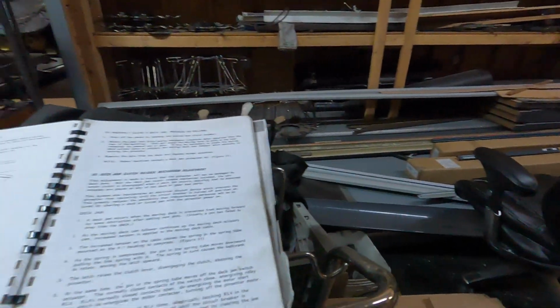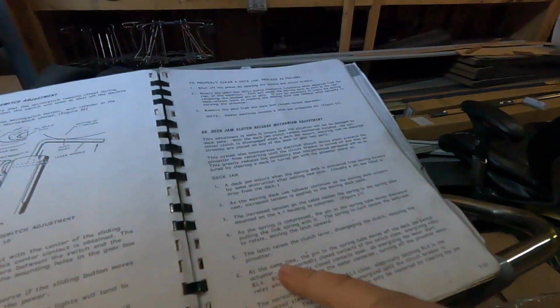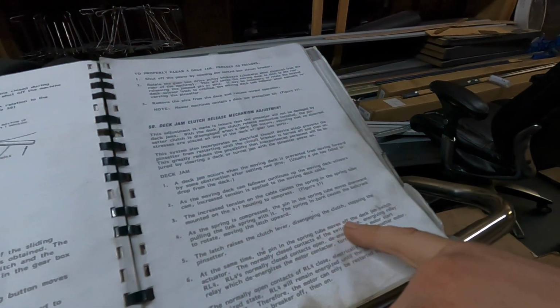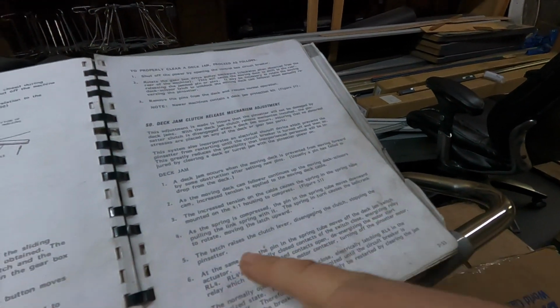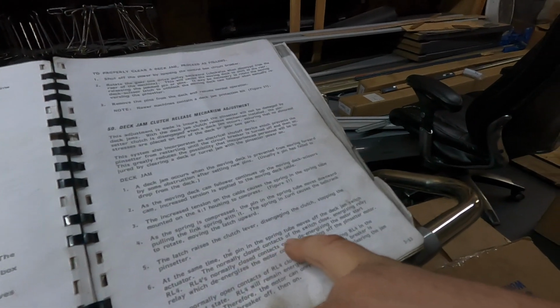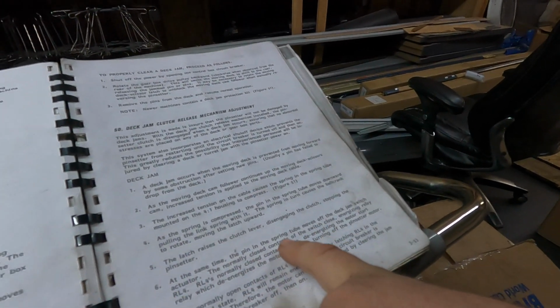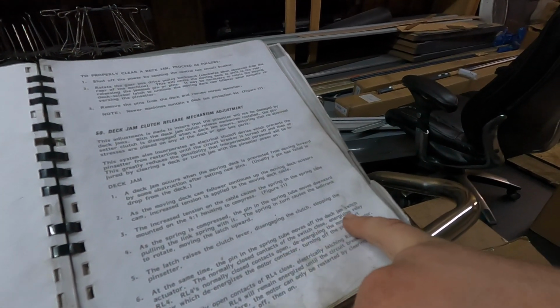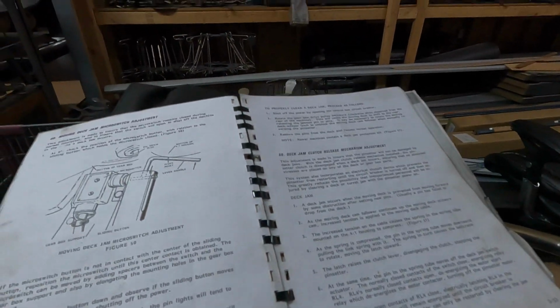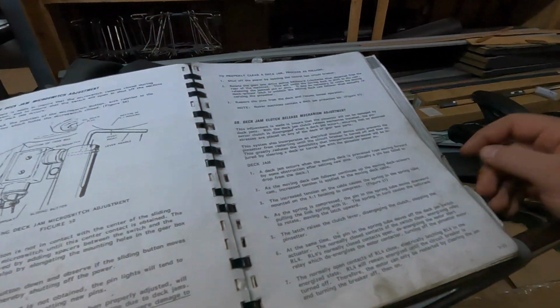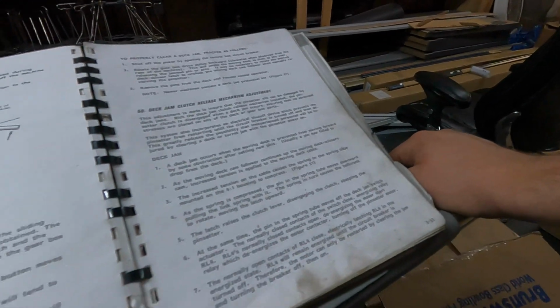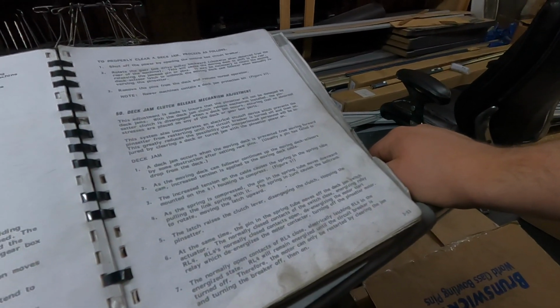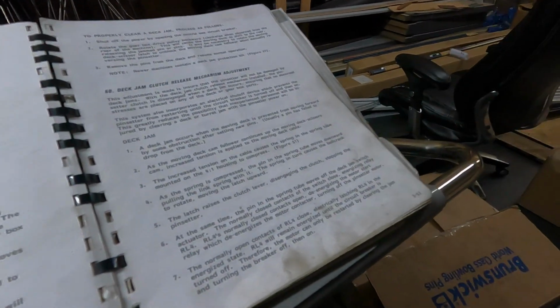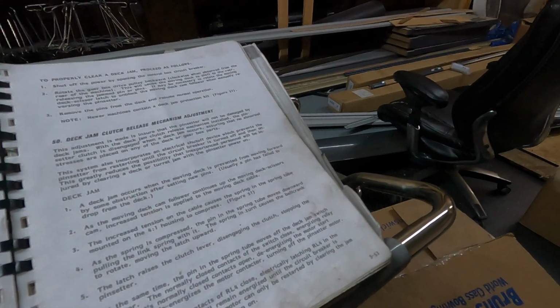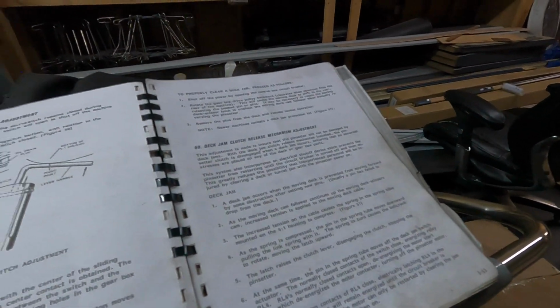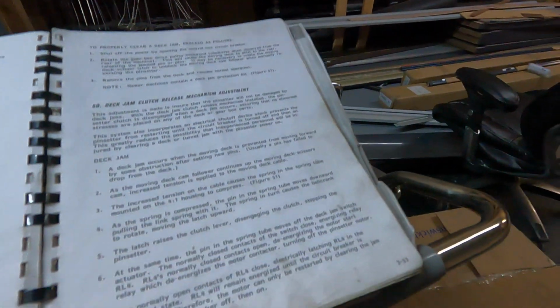Pretty self-explanatory, I guess. At the same time, the pin in the spring tube moves off the deck jam switch actuator. The normally closed contacts of the switch close, energizing relay RL4—I couldn't tell you which one that is off the top of my head. RL4's normally closed contacts open, de-energizing the motor. Oh, which one? That's the start relay.